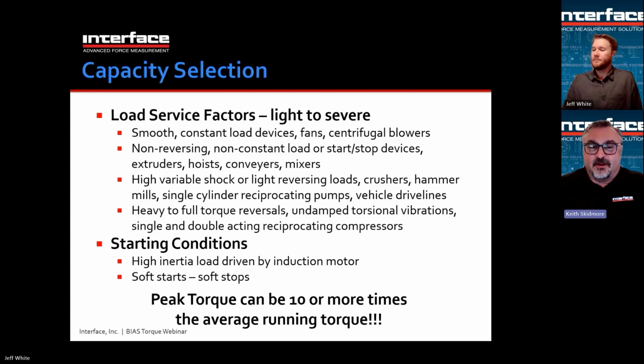And that may be something too that a motor test might want to measure. So you basically lock a brake, turn on the motor, and see what the torque is. That can be a lot higher, as in 5 times higher, 2 times, 3 times higher than the actual rating of the motor. And then same thing when you stop.